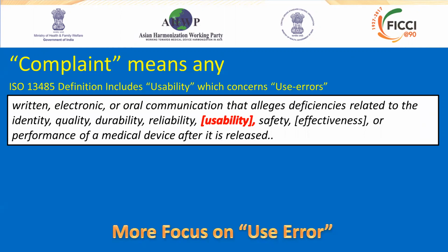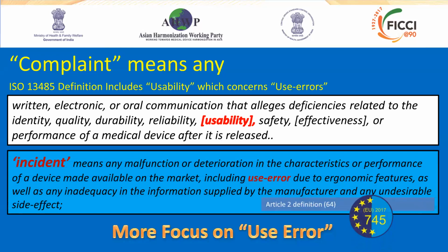So everyone needs to be taking into account, when they get a complaint from someone, if there was a problem related to their confusion in operating the device that led to the issue, those need to be handled as complaints. The European regulation uses the word incident as meaning a malfunction or deterioration in the device or its characteristics and performance, including use errors again. So all throughout the new regulations and standards, we're seeing a lot more focus on use errors.